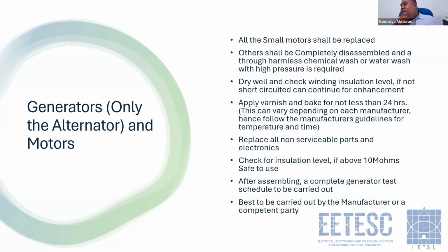For the generator, you will have to do a load test, insulation test, and all sorts of tests that you do for your commissioning work. And again, I'm telling you, it is best carried out by the manufacturer or a competent party recommended by the manufacturer, or someone you have experienced.